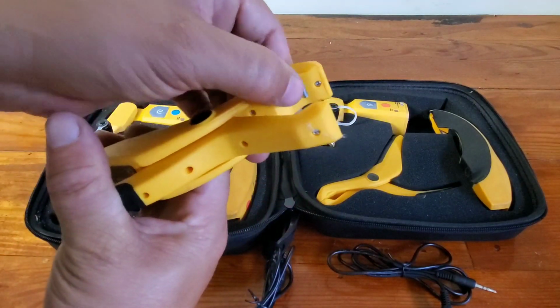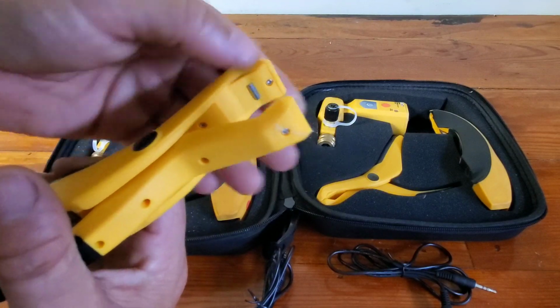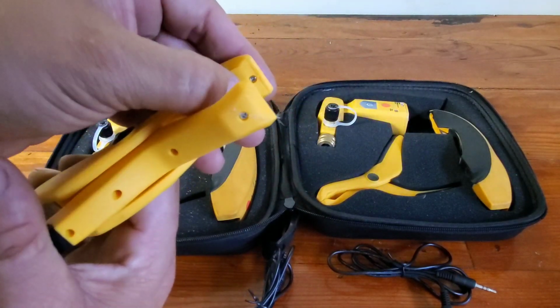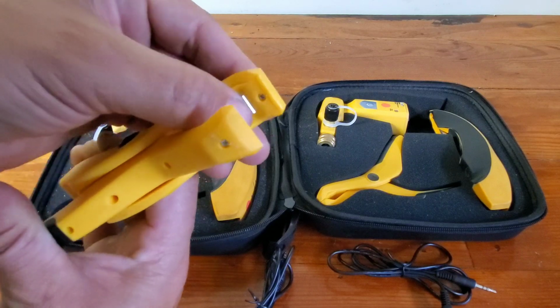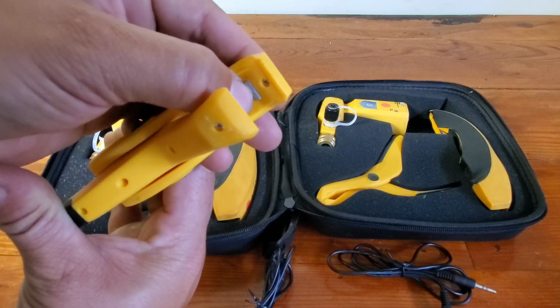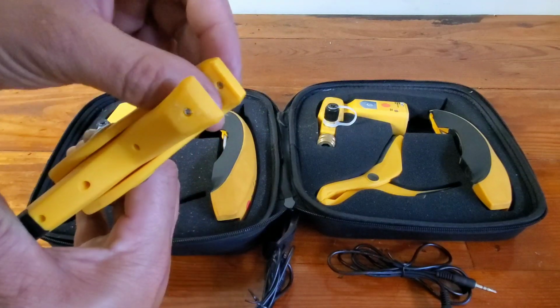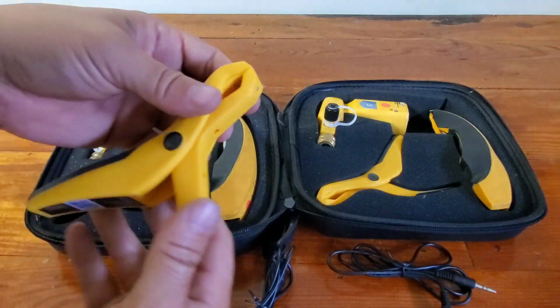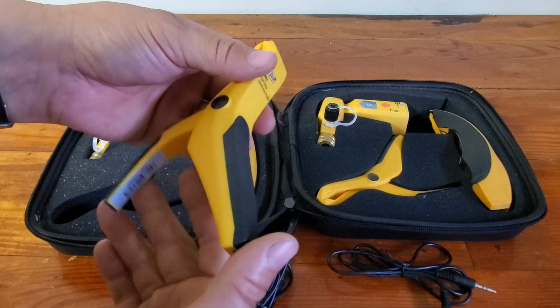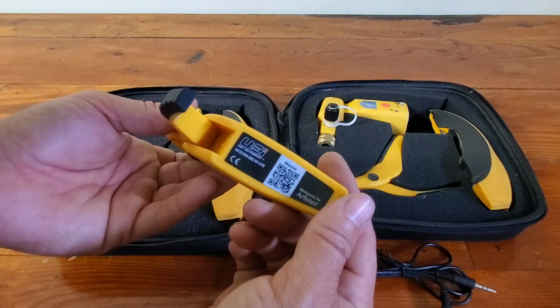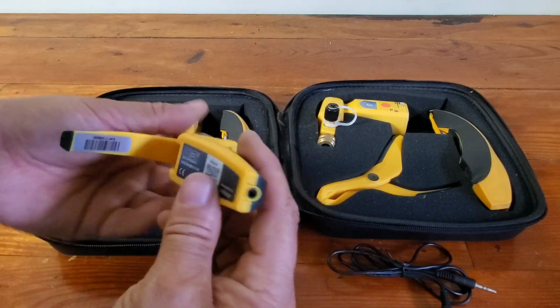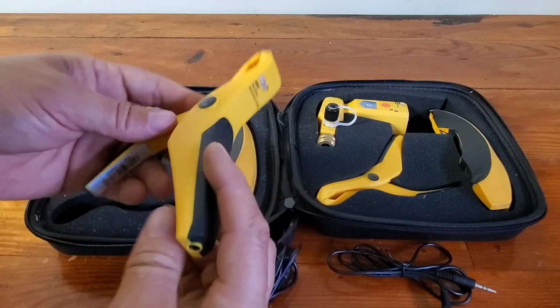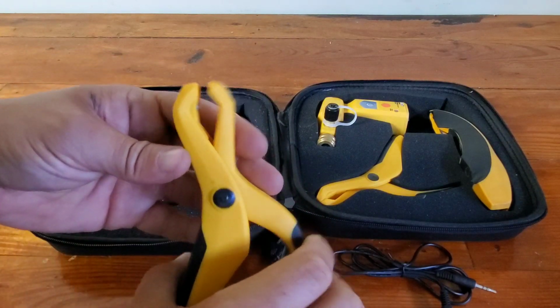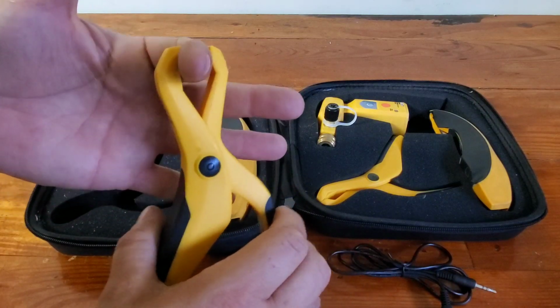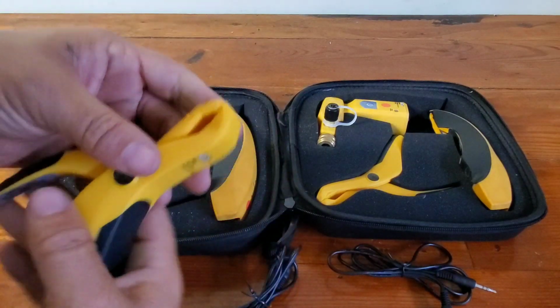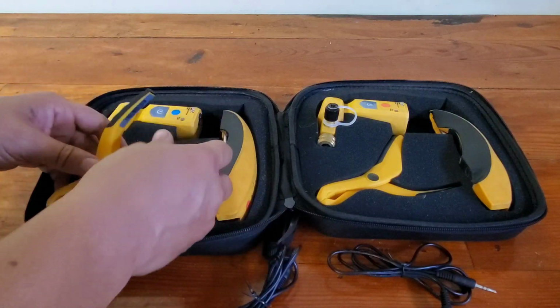You can see our thermistor right there, and it's actually spring-loaded. It's going to be hard to see, but it's spring-loaded, so it gets a nice consistent contact with the pipe. Here's our jack where we would hook the tether from the transducer to the clamp, but pretty straightforward. It's got quite a bit of grip to it, but that's the clamp.